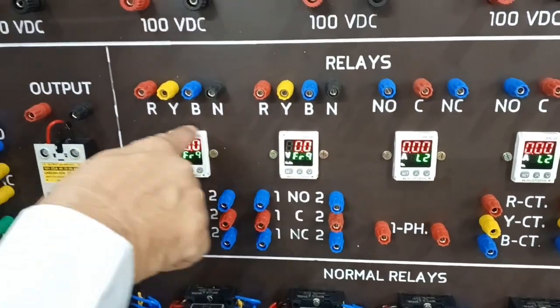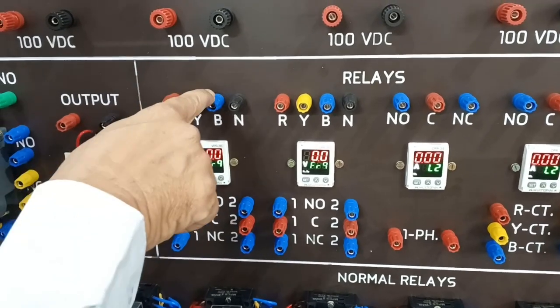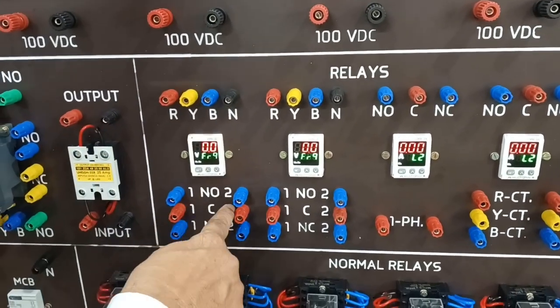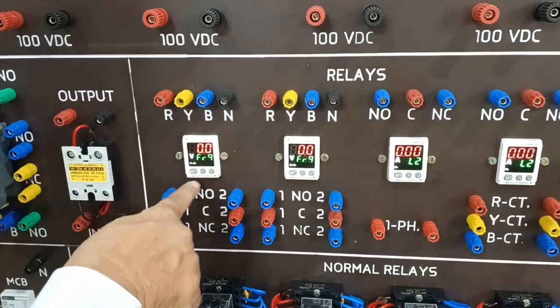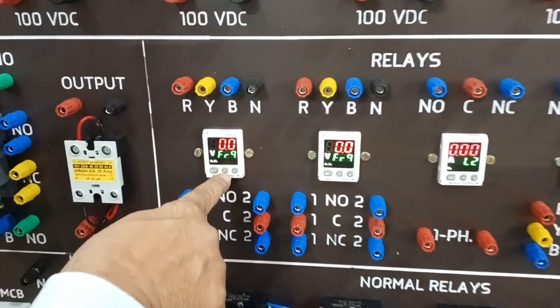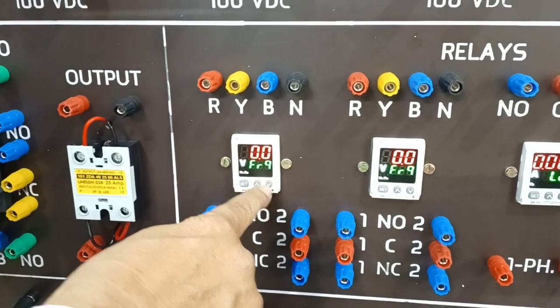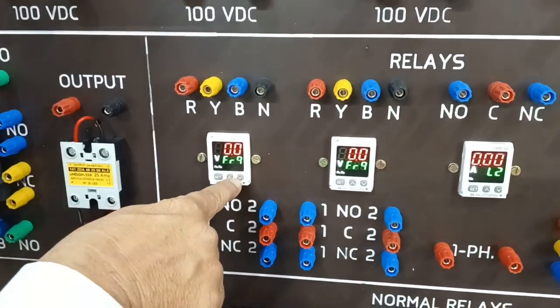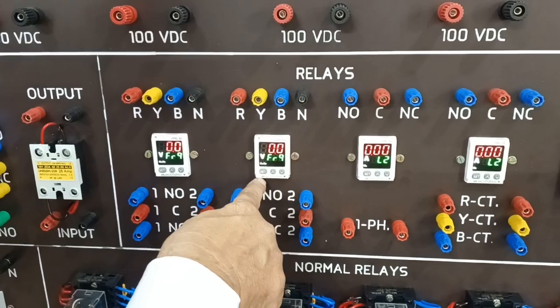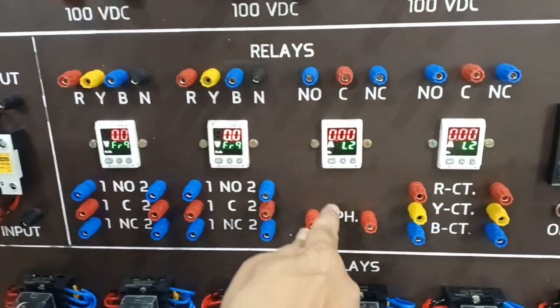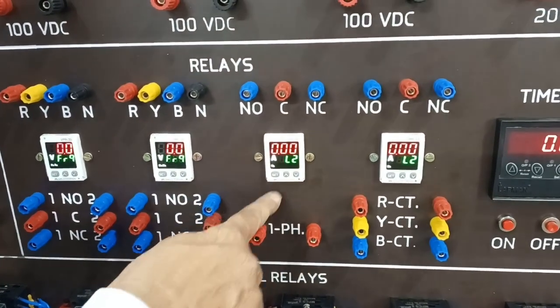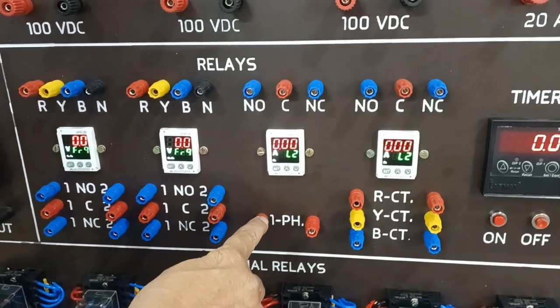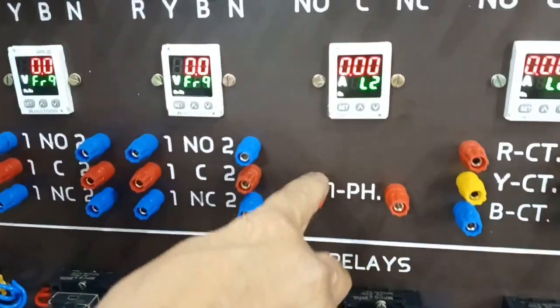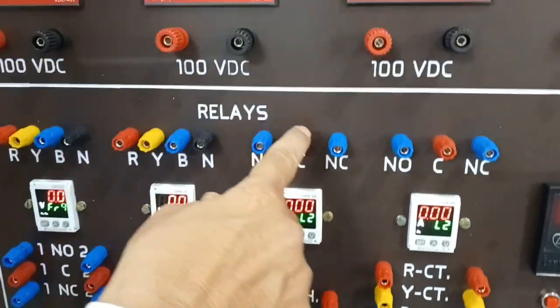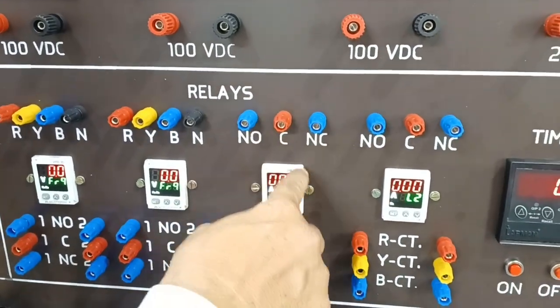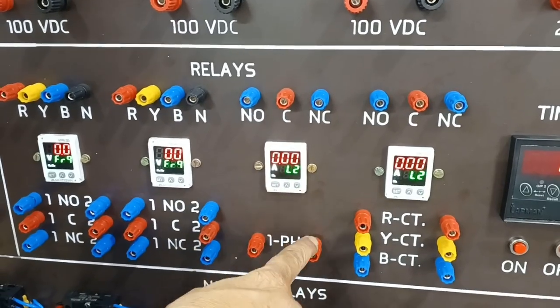Say to sense with this relay, you need to apply 3 phase and a neutral, and these are all the contacts. Say to operate this or to set the fault voltage, you need to do programming. This programming video will be shown to you later. This is also a 3-phase under over voltage relay, and this is a single phase over current relay. So for sensing current, you need to apply across this, this is CT primary. These are all contacts, common, NO and NC of the relay. You need to program according to your requirement.